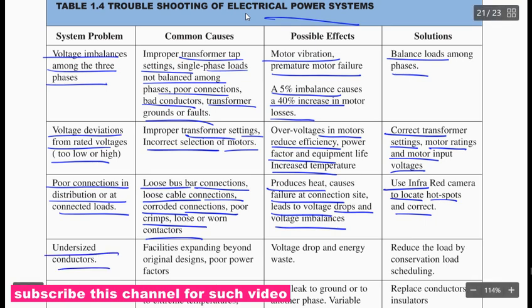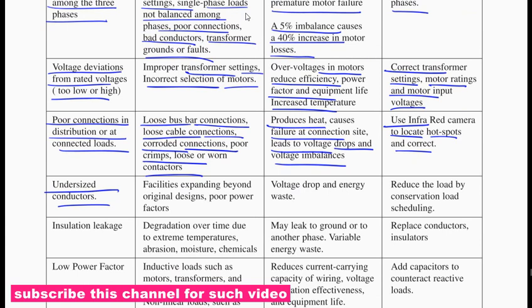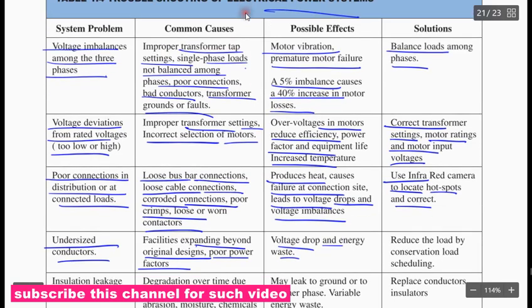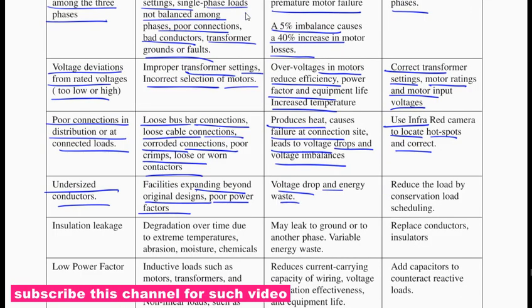Undersized conductor. Common causes: facility expanding beyond the original design. Possible effects: poor power factor, voltage drop and energy waste. Solution: reduce the load by conservation and load scheduling.